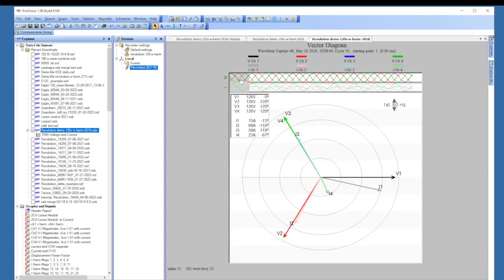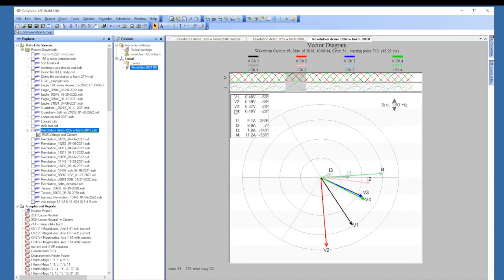Now we are only looking at one cycle. You can move that over. But here too, if your Flex CTs are on backwards, you'll see these about 180 out from where they are. So if they're close together like they are, then you know your Flex CTs are on good. You can also change to a harmonic in here and see what your harmonic is. Now again, we're just looking at one cycle.